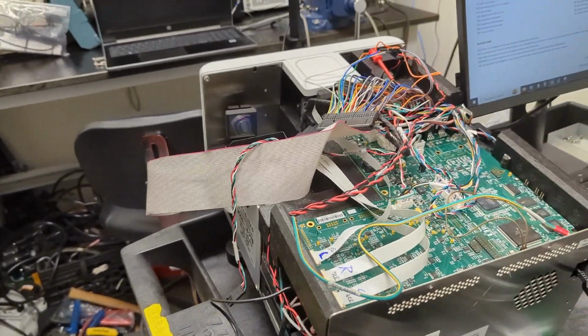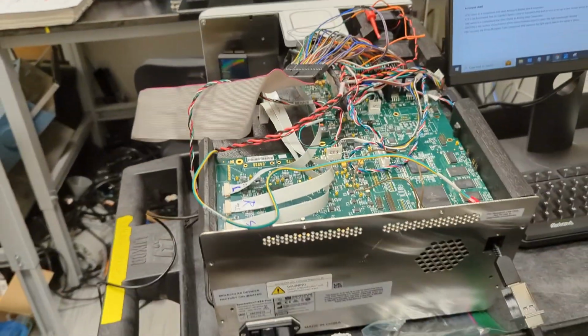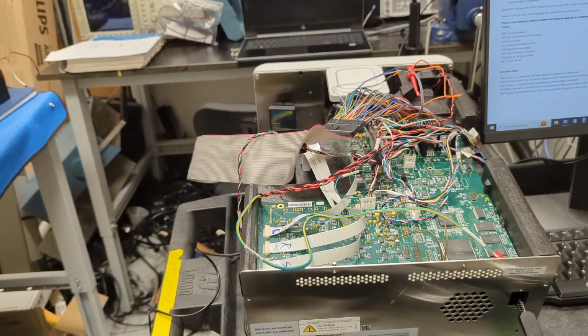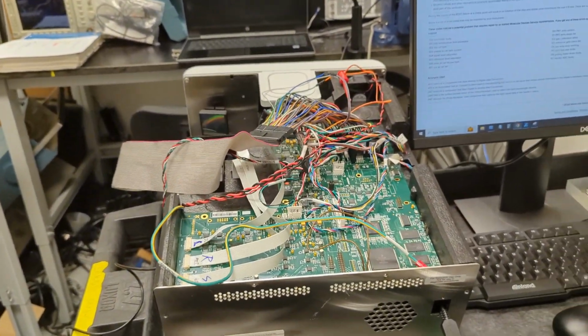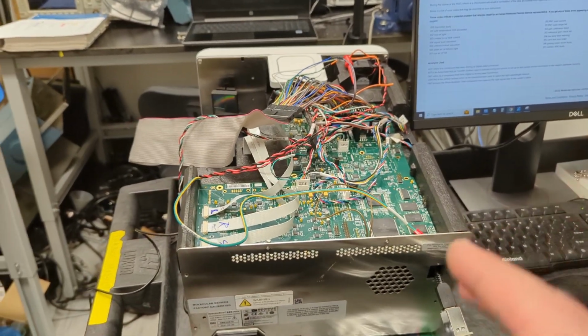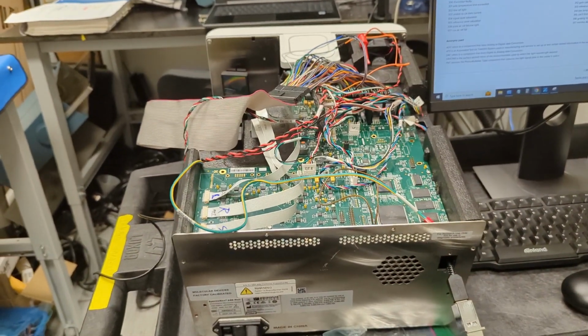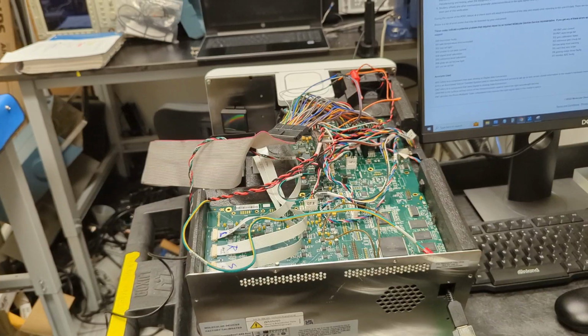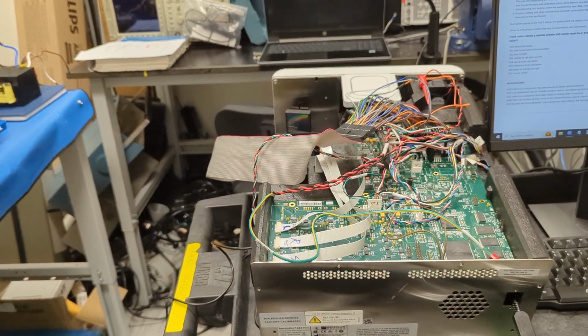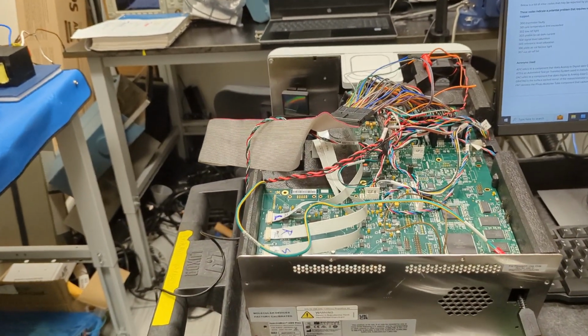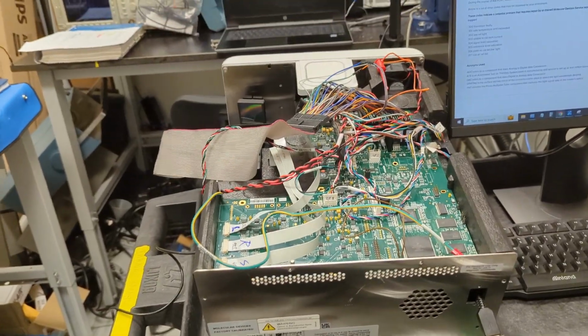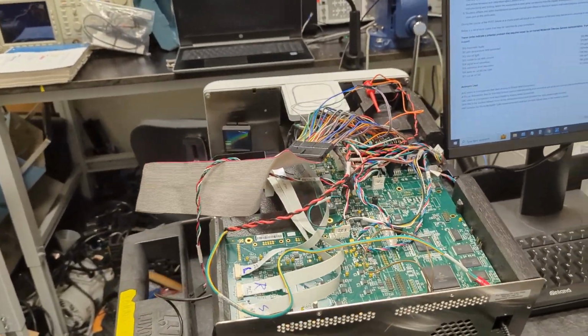Now, the issue with this instrument: it started during the startup of this instrument, it was giving this error. It named it a 401 error, which is a filter wheel error, according to the manual, and I have that pulled up here.